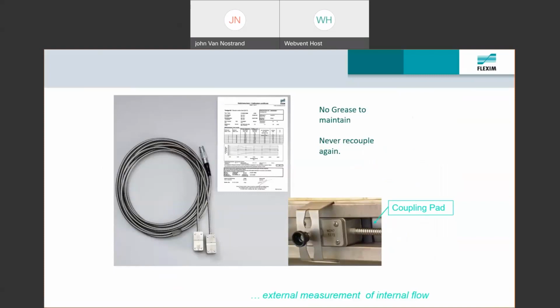I mentioned earlier that we use a robust armored cable. This is what it looks like. It's like a stainless steel braided cable. And the SensPROM holds the calibration data. You see the calibration certificate here in the upper right-hand corner. That shows us the cal cert that you're going to get with the transducer. And these are portable transducers. So the SensPROM that holds the data for the calibration is integrated into the cable. So when you plug that into any of your portable flow meters, that data is automatically going to load in, and there's nothing that needs to be done. It's a smart coupling of the transducers in the flow computer. Additionally, it shows the coupling pad here. This is what the coupling pad looks like versus the grease. So it's a set it and forget it.